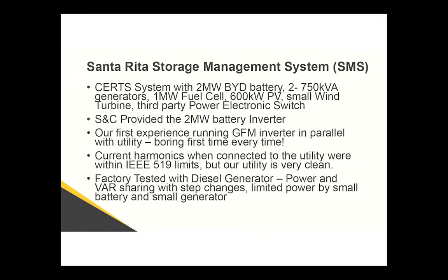So the next system that I wanted to talk about was the Santa Rita jail microgrid system. So this is a system using CERTs that had a 2 megawatt lithium-ion battery from BYD, a Chinese company, 2 750 kVA diesel generators, a 1 megawatt fuel cell running in the grid following mode, and 600 kilowatts of PV also running in grid following mode. The diesel generators were normally not on, and then what S&C provided was the battery inverter.